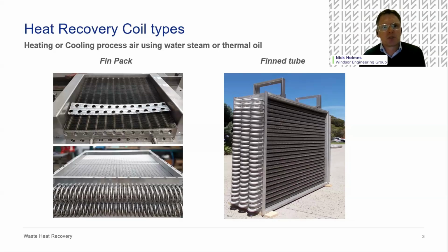What I'm going to pursue today is purely a finned tube type heat exchanger. It's predominantly used for heating or cooling air streams, process air. They can be used for slightly different applications, but nearly always they're using a heating medium like hot water or chilled water or possibly steam to add heat or to recover heat from a gas stream. And when I say gas, it might be a clean air process or a dirty exhaust from a dry process of some sort.